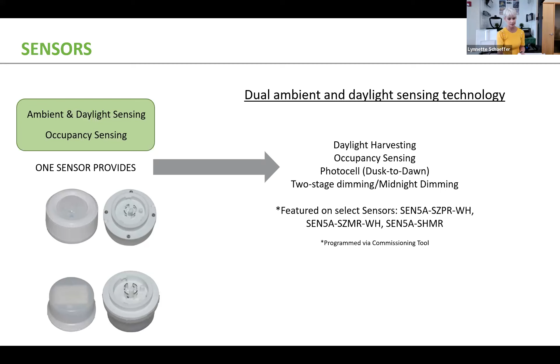The only slight thing is you have to use the commissioning tool. This is the old one - I accidentally grabbed it. Anyway, there's a new commissioning tool, I didn't even know I had this one yet, but there's a new commissioning tool you'd use to program these based on whether you want daylight harvesting, occupancy sensing, photocell, two-stage dimming, or whatever. I'll get into more details about that in just a second.